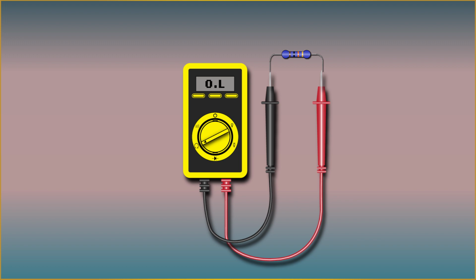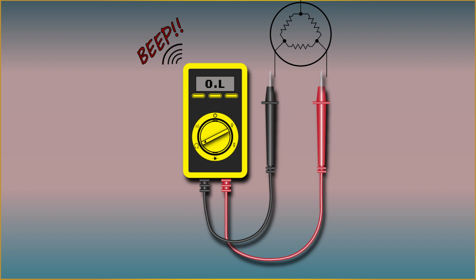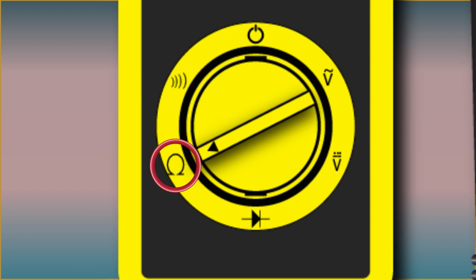That's also how your meter does continuity. It sends a DC voltage out on the red lead, and when it receives it back on the black lead, it powers a buzzer inside of your meter. Knowing that, you should start to get used to using the ohms resistance scale on your meter whenever you're checking motors or other coils, not continuity. Continuity is for switches and small distances. If you have a very large distance or a very big coil, continuity might not be powerful enough and may give you a false negative. You should always check motors with resistance, not just continuity.